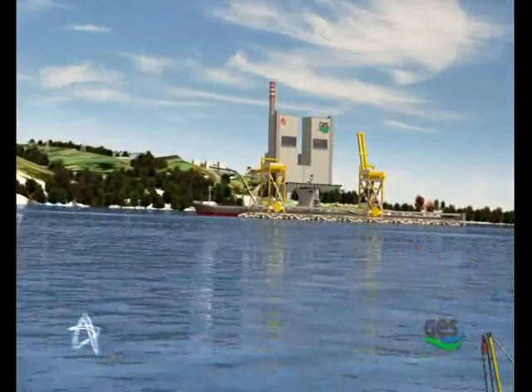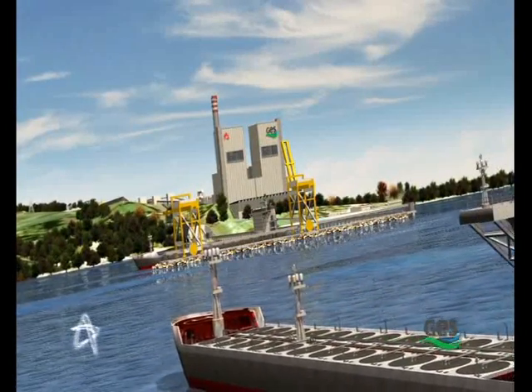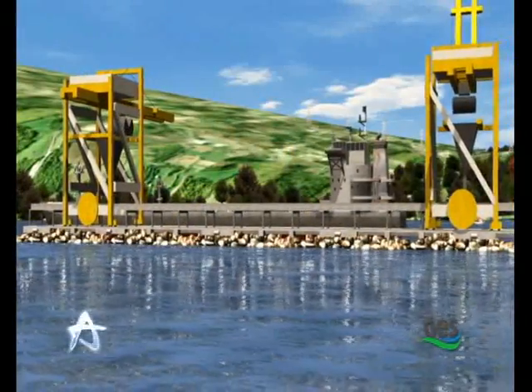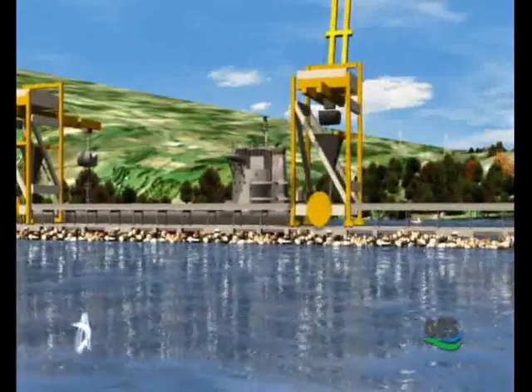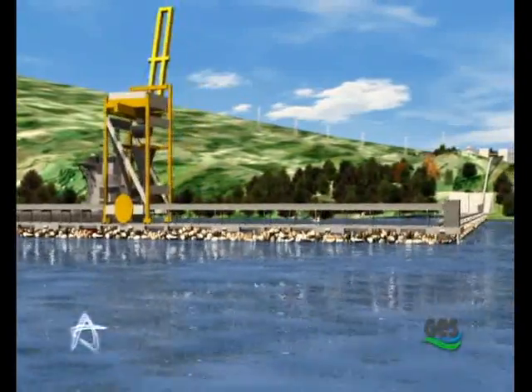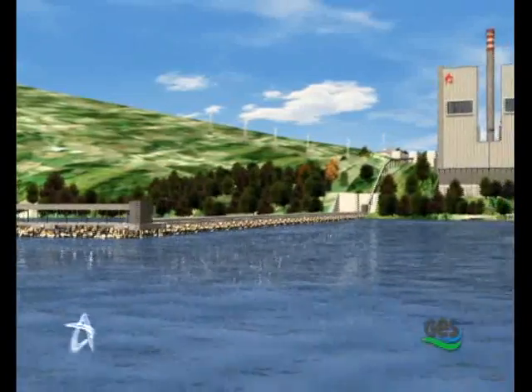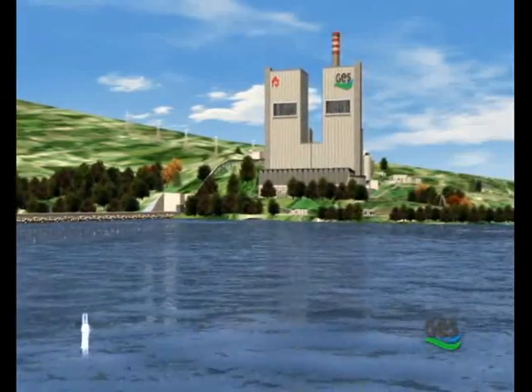Gerze power plant will generate electricity using high calorific value, low ash content, imported coal. The advantage of burning imported coal with supercritical steam technology is twofold. First, supercritical power plants operate at higher temperatures and pressures and are 35% more efficient than today's fleet of coal-fired plants. That is, they would use 35% less coal for the same power generation and emit 35% less. Secondly, utilization of imported coal instead of low calorific value coal further decreases the coal consumption and hence emissions. As a result, Gerze power plants will operate at lower emission levels than those of the European Union standards.